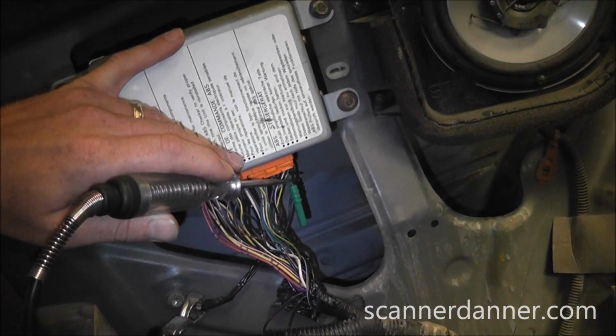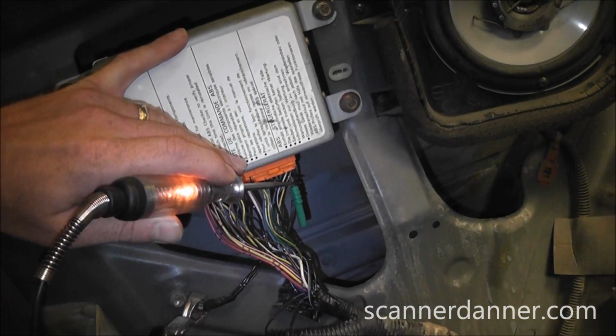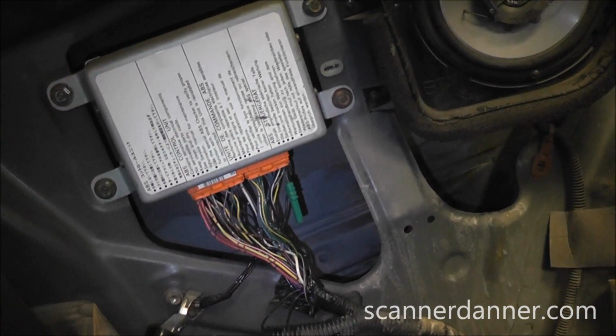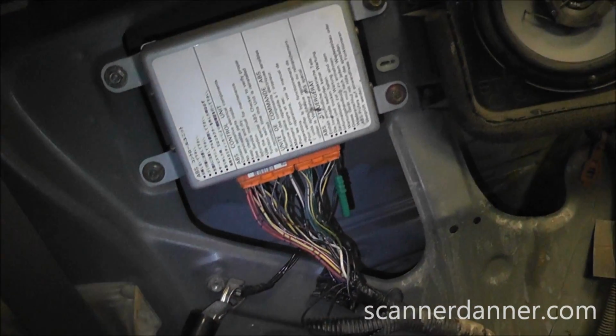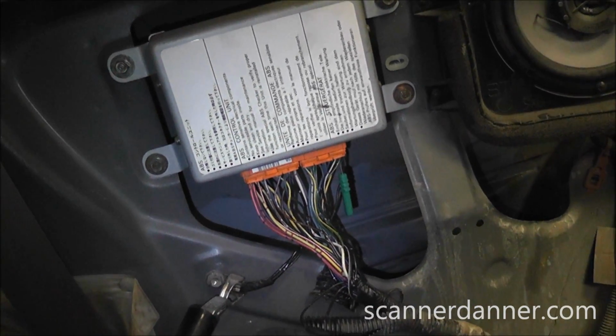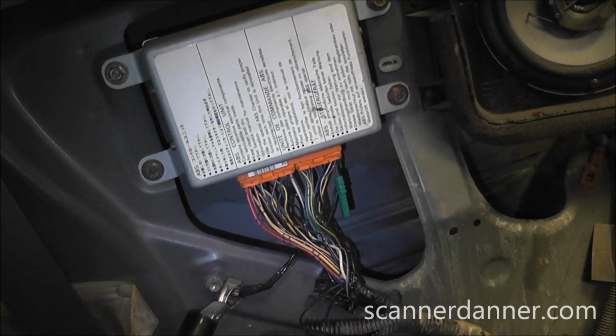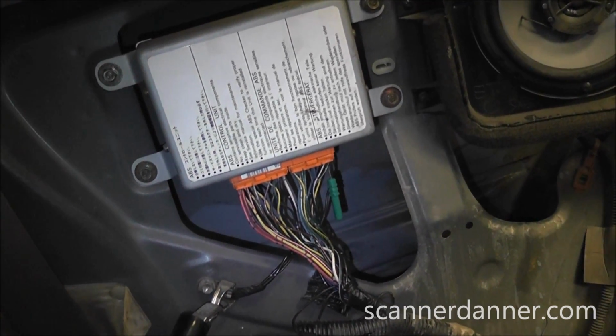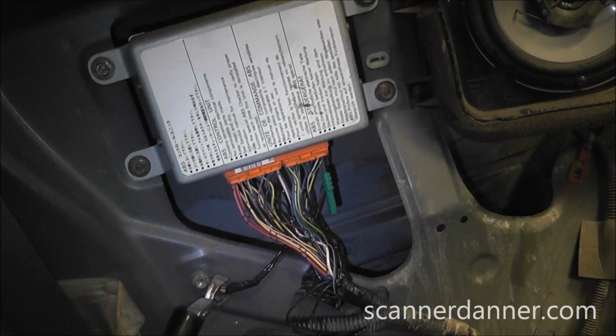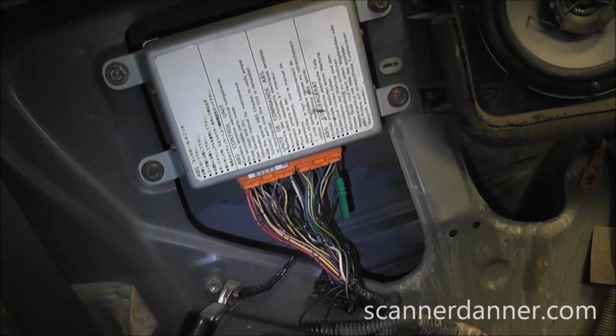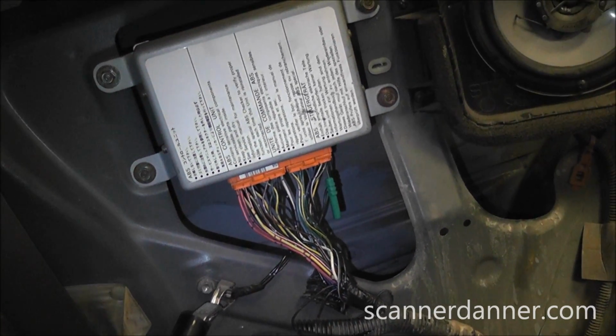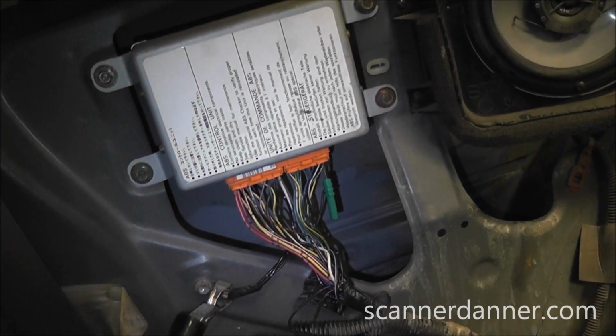You see my test light just barely lighting. It's dim, and the reason for that is we're not dropping all of the voltage across the coil of that relay. Most of it though, it's enough to energize it. I heard the relay click. So I'm going to go up front and show you these voltage readings while I'm energizing this back here.